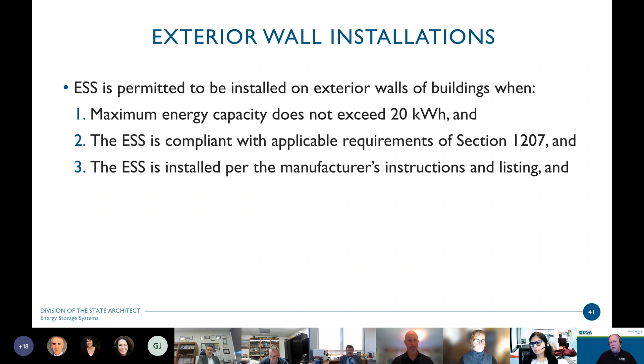And outdoor, again, as I mentioned at the early onset, also includes exterior wall installations. So yes, smaller units can be attached to the exterior wall of buildings. These are, however, limited in capacity to 20 kilowatt hours. And the ESS has to be compliant with the requirements in 1207. And when we're talking about pieces of equipment, just like many other DSA elements, it has to be installed per the manufacturer's instructions and listing. So in addition to the code requirements, you're certainly going to want to incorporate any of the manufacturer's requirements.